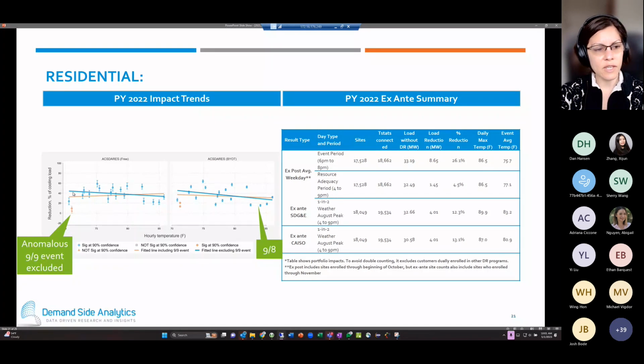So we chose to exclude those points from the ex ante model, because across all these points you're looking for a trend of reduction as a function of temperature. If you include these points, it actually tips that trend quite a bit - the orange line is the trend. Including them it's relatively flat; excluding them it's declining a little bit. As temperatures get hotter, overall reductions do still increase, but as a percent of cooling load they decrease slightly. Including those orange points would overestimate the reductions, so we excluded them from this estimate.